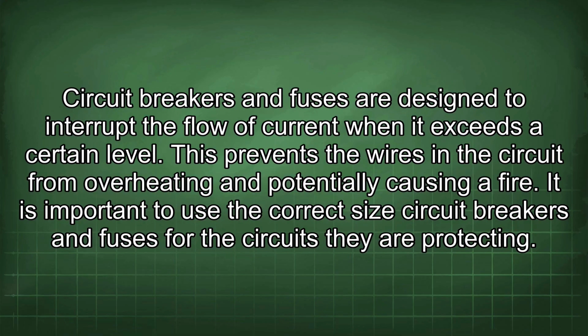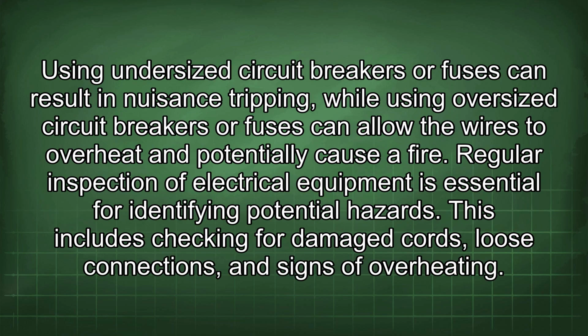It is important to use the correct size circuit breakers and fuses for the circuits they are protecting. Using undersized circuit breakers or fuses can result in nuisance tripping, while using oversized circuit breakers or fuses can allow the wires to overheat and potentially cause a fire.